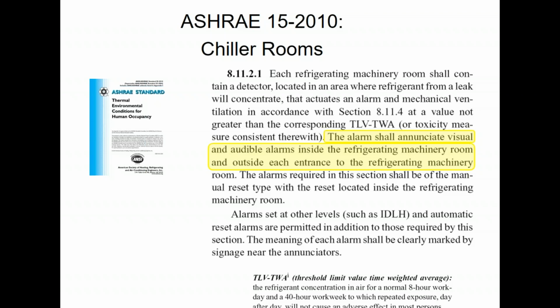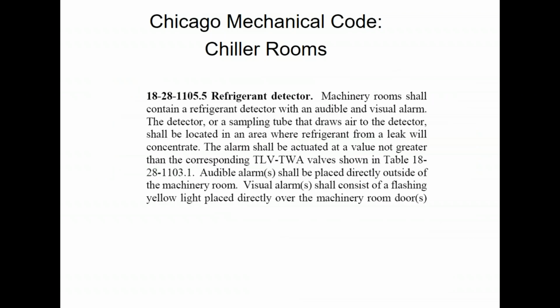But in this case, a chiller room, I need to have the ability to monitor refrigerant for leak potential. I have a very large quantity of refrigerant in a fairly small room, so I have to have sensors in there to detect if refrigerant leaks. Additionally, the alarm shall annunciate both visual and audible alarms inside the room and outside every entrance to the room, right? So what does that look like for an actual project, if you will?